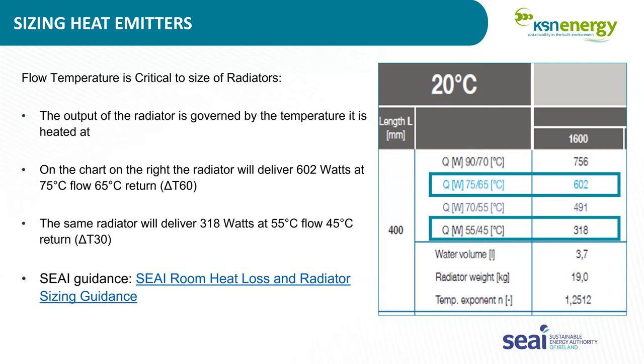If we take that snip from a radiator sizing chart, you see manufacturers will state what the flow and return temperature of a radiator is, or they might put it in the delta T. They have a couple of different ways of describing it. We can see that 75, 65 would be a conventional, standard efficiency boiler. For that radiator, which is probably 400 by 1600, you'll get 600 watts of heat out of that. But at a reduced temperature, perhaps if it was a heat pump, it's only 318 watts. So in some cases, people may need to replace radiators.